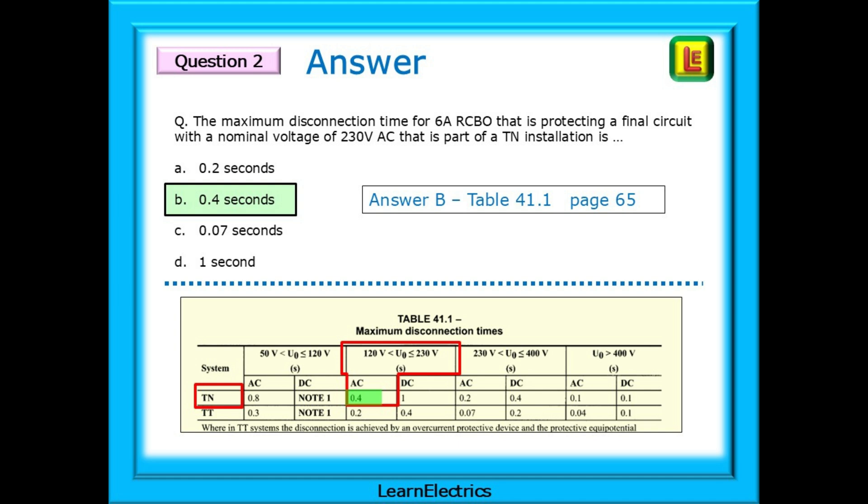The answer choice is B, 0.4 seconds, as found in table 41.1 on page 65. Look in the index at the back of the book, page 583. Find disconnection times, find final circuits and you are directed to table 41.1. The rest is a simple case of cross-referencing the table.